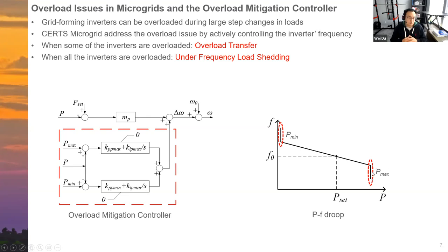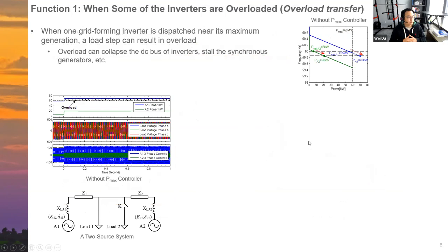This controller has two functions. The first is overload transfer. When some inverters in a microgrid are overloaded, this controller can autonomously transfer the extra load to other inverters. And when all the inverters in the microgrid are overloaded, this controller can activate under frequency load shedding. But let's talk about the first function, the overload transfer.